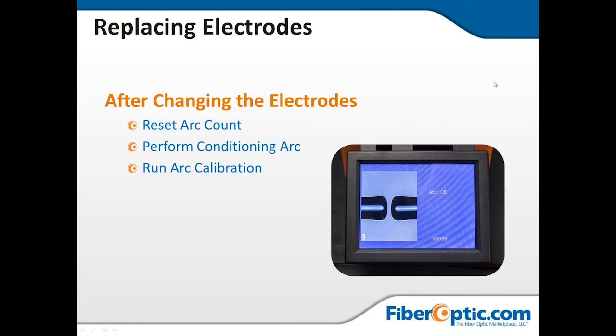After changing the electrodes, there are some things you need to do. One, you can reset your arc count. Two, perform conditioning arc. This is basically in the menu of splicers. There is an electrode stabilizing setting. It is important that you stabilize your electrodes. This basically gets them primed for working properly.